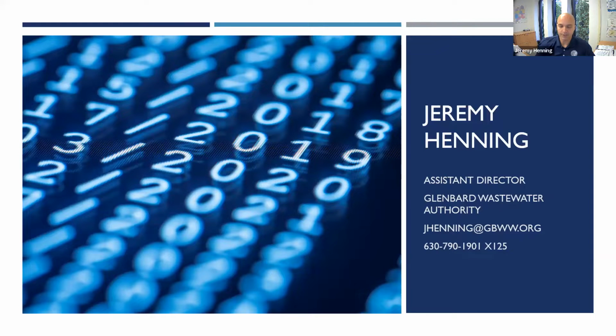The operator monitoring can wait probably 45 minutes to an hour total—hopefully that's an acceptable window, though you'd determine what's right for you—past that restore time. If it's been 45 minutes or an hour and they still don't have communications back, now we can call the service provider and say we've already done a reboot automatically via PLC control, so there's something else going on here. It definitely saves some truck rolls. Again, sometimes it's out-of-the-box thinking to implement something that fixes a problem for you.